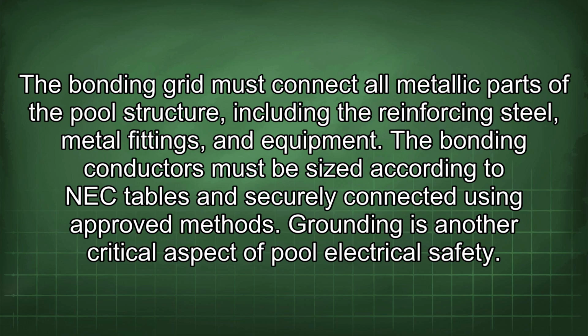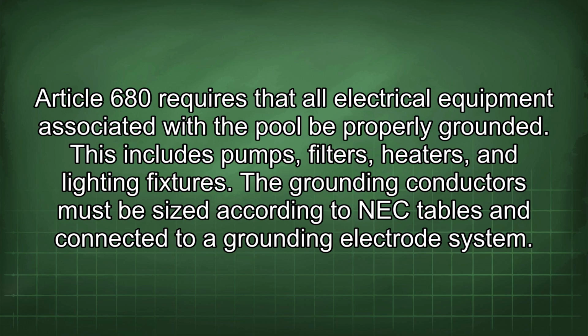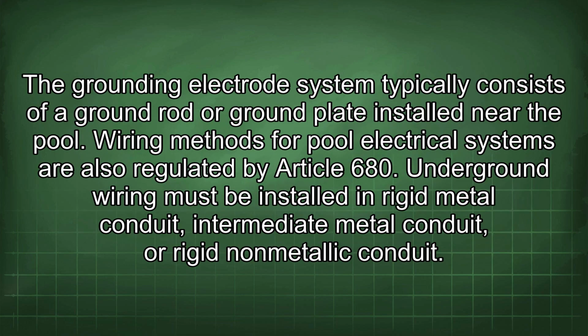The bonding grid must connect all metallic parts of the pool structure, including the reinforcing steel, metal fittings, and equipment. The bonding conductors must be sized according to NEC tables and securely connected using approved methods. Grounding is another critical aspect of pool electrical safety. Article 680 requires that all electrical equipment associated with the pool be properly grounded. This includes pumps, filters, heaters, and lighting fixtures. The grounding conductors must be sized according to NEC tables and connected to a grounding electrode system. The grounding electrode system typically consists of a ground rod or ground plate installed near the pool.